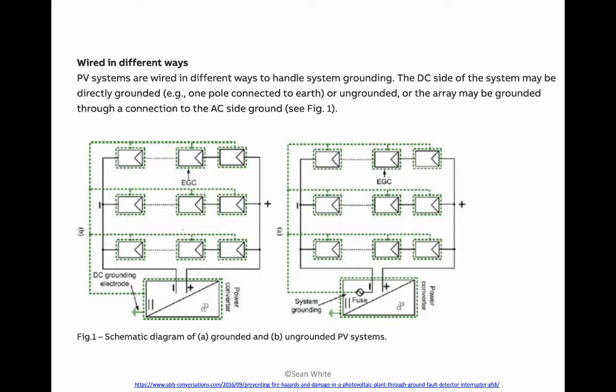So then we started to adopt these inverters, and we called them ungrounded inverters, and we had to put a special label by the inverter that said, "Warning, ungrounded inverter." And that was kind of scary too. And we got rid of that warning sign also in the 2017 NEC when we started calling both of these types of inverters functionally grounded inverters.